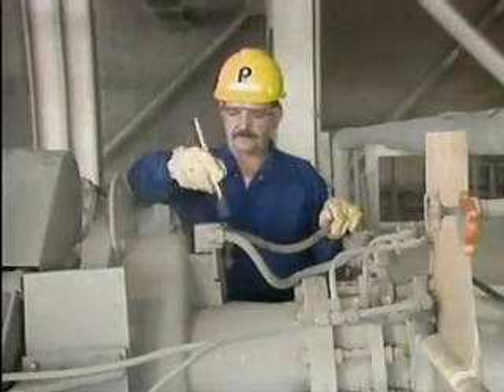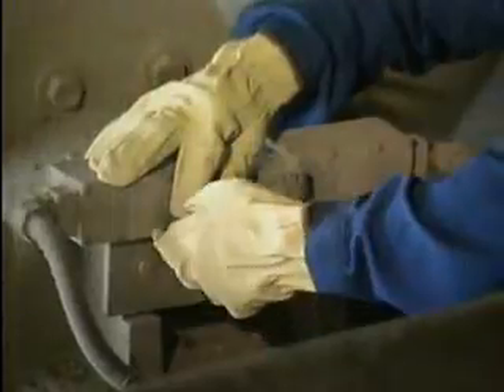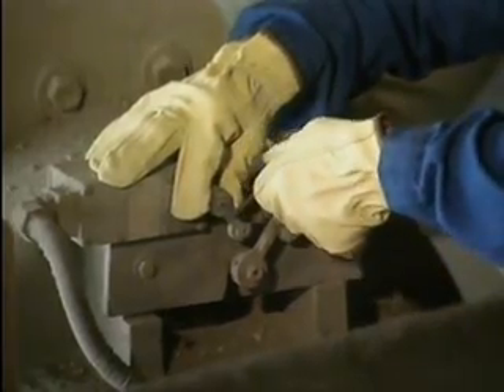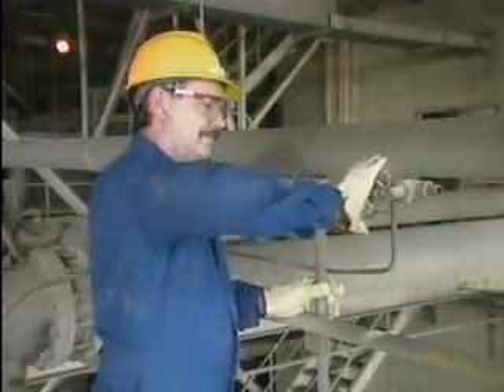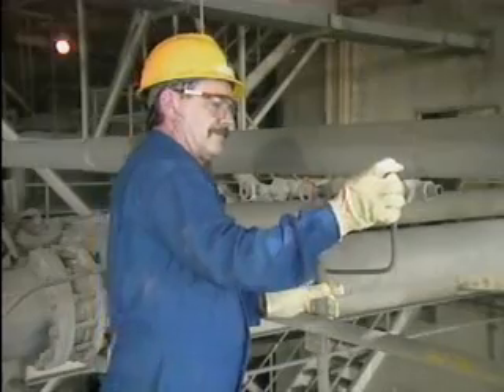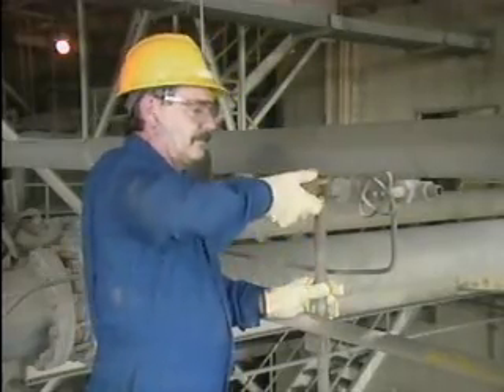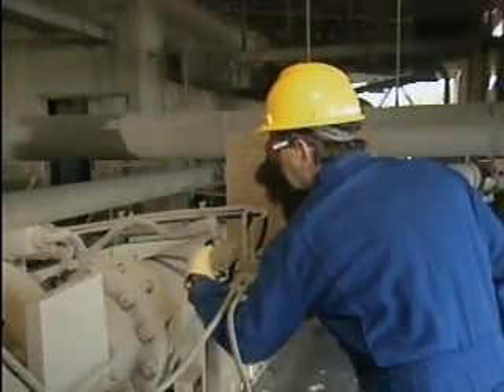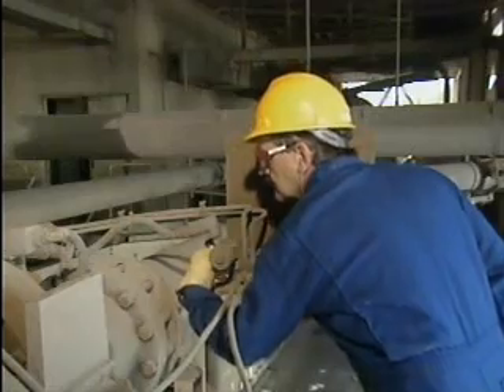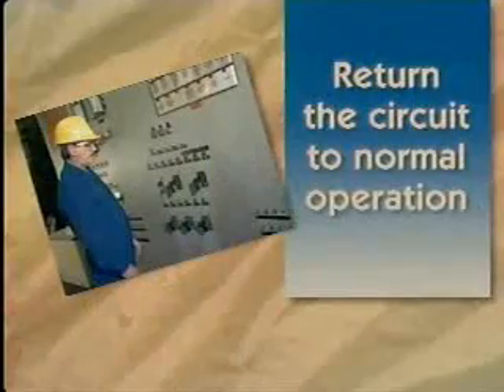He corrects the problem by cleaning the valve and repositioning the loose limit switch control arm. Then he closes the bleed valve and turns the valve's air supply back on. He switches the valve to its manual override mode to test the operation of the valve. Then he returns the valve to its automatic mode. All that's left to do is return the circuit to normal operation.